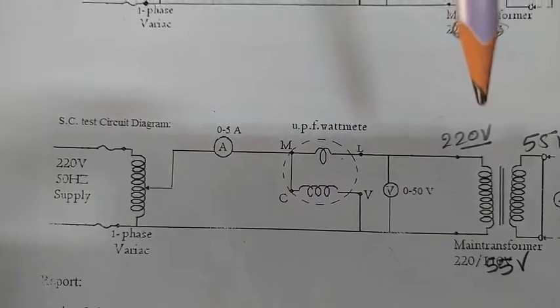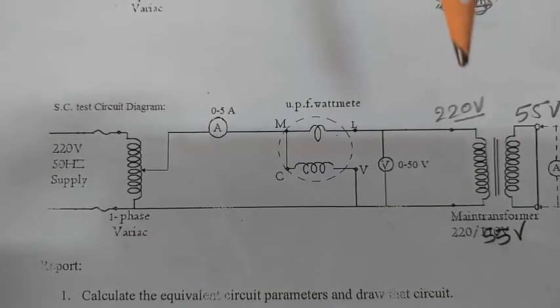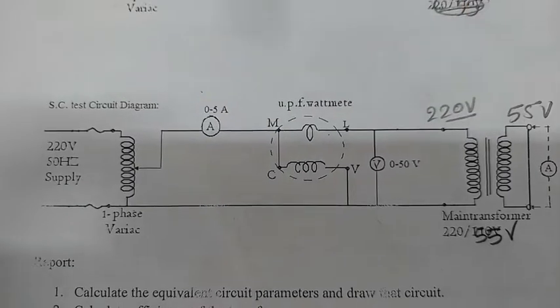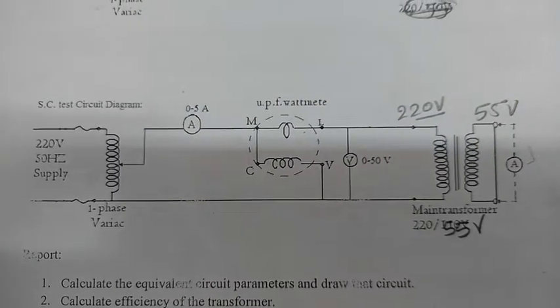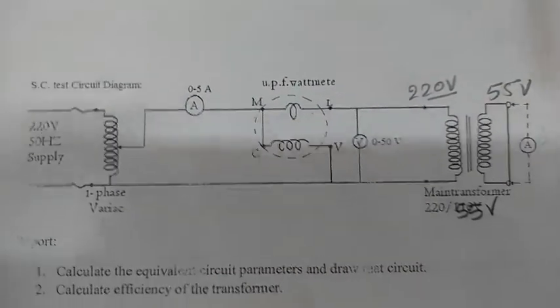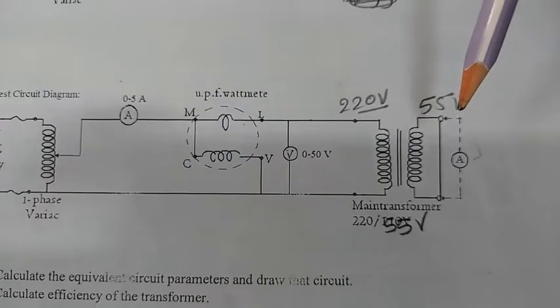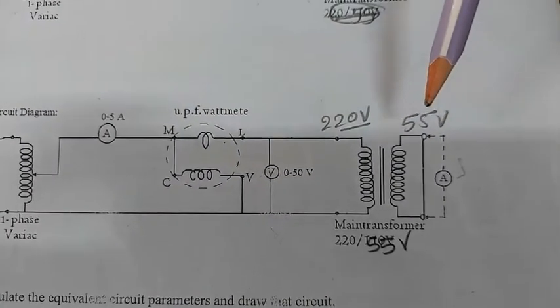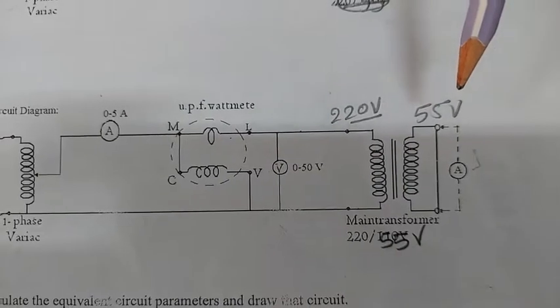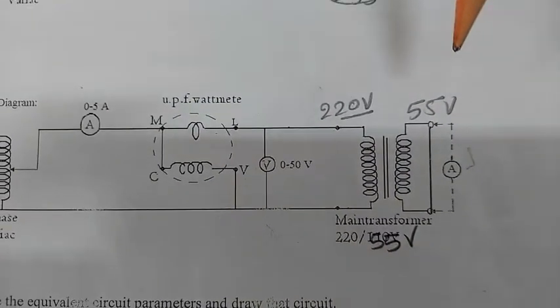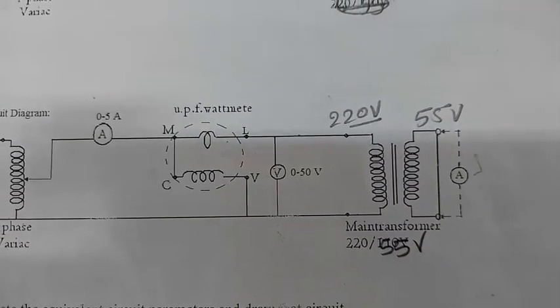So 5 to 15% of the 220 volt will be the minimum required voltage to send the full load current through the secondary, that is the 55 volt side. So how to get the reading of the secondary winding? Because we have already connected the ammeter, so we will get the ammeter reading and we will get the current.